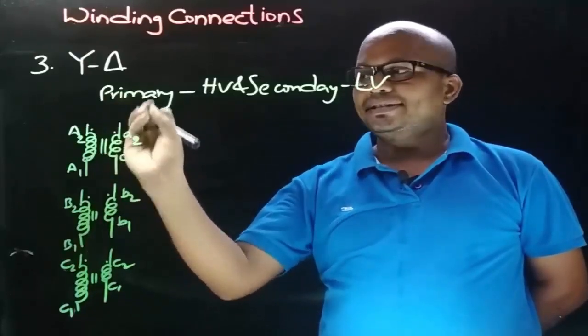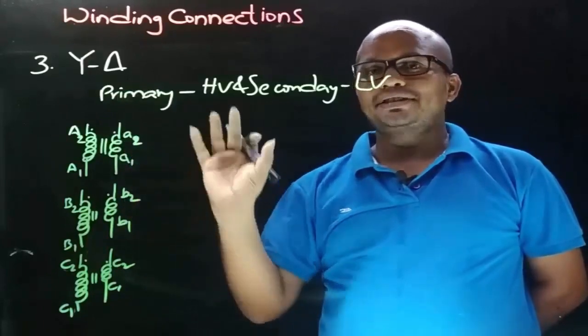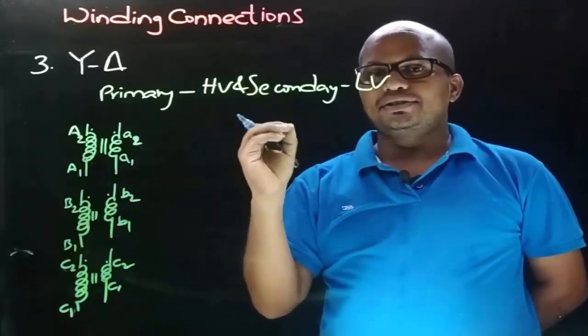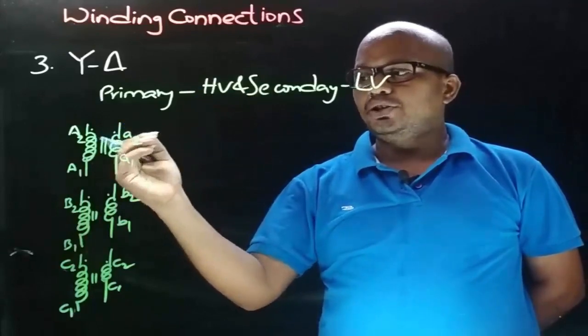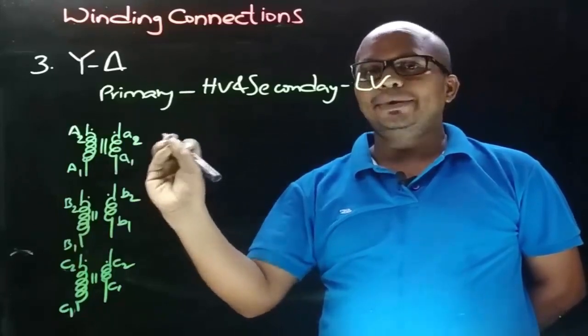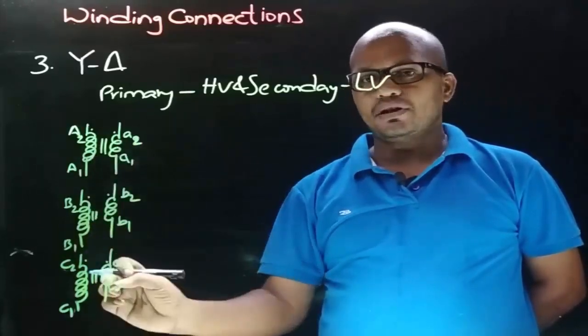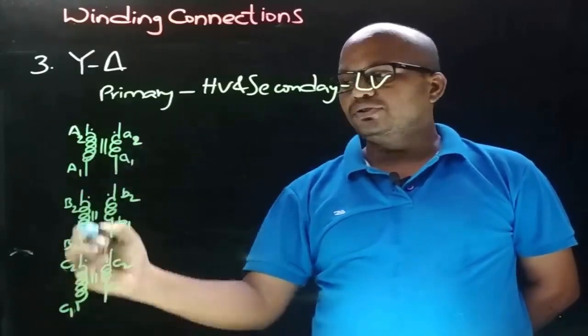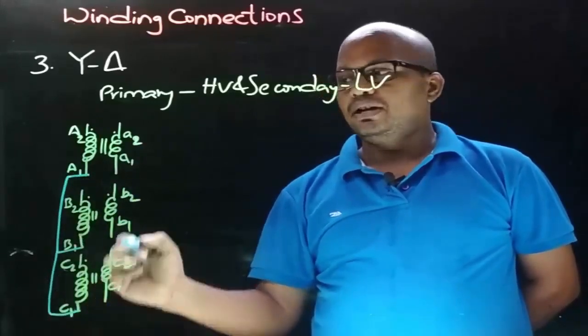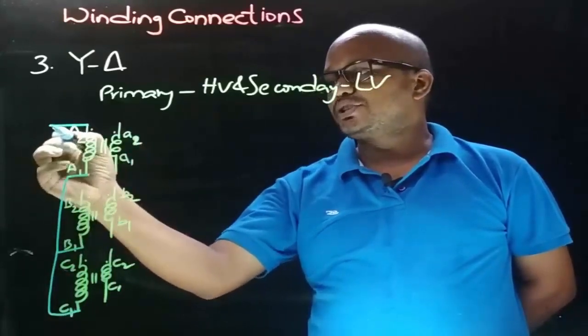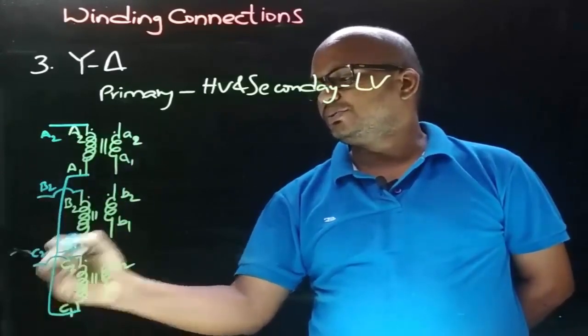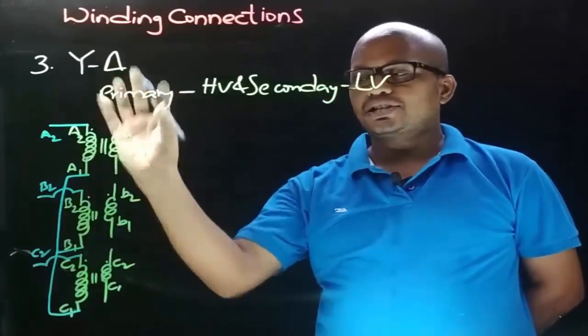First let's obtain the star connection on the primary side. To obtain the star connection on the primary side we must join the common end terminals and take the connections from the other ends. The common ends could be dot ends or non-dot ends. Here let's consider the non-dot ends as the common end terminals, which are A1, B1, and C1. So join A1 to B1 and then to C1, and take connections from dot ends A2, B2, and C2. We obtain the star connection on the primary side.